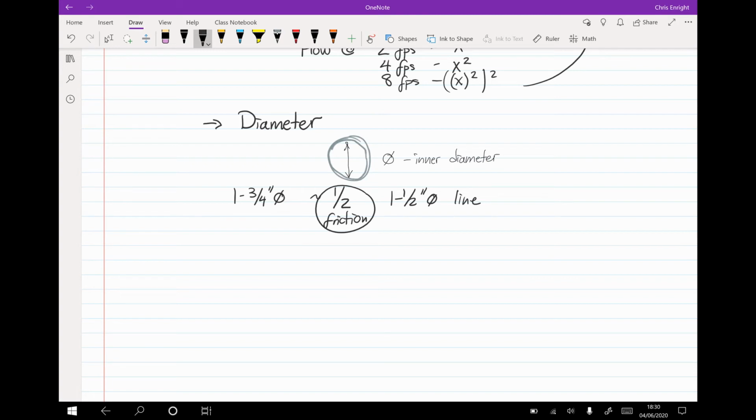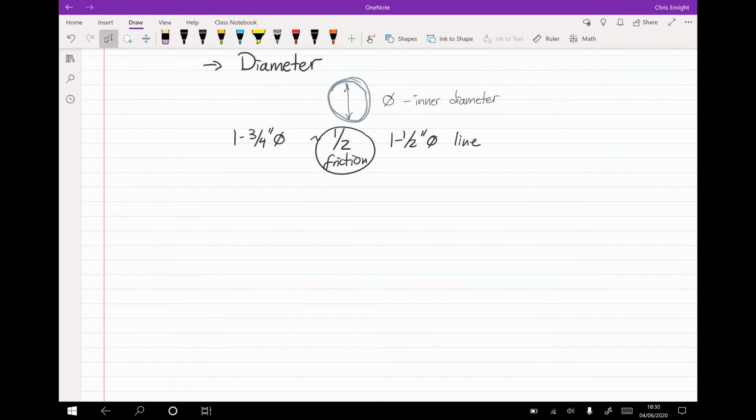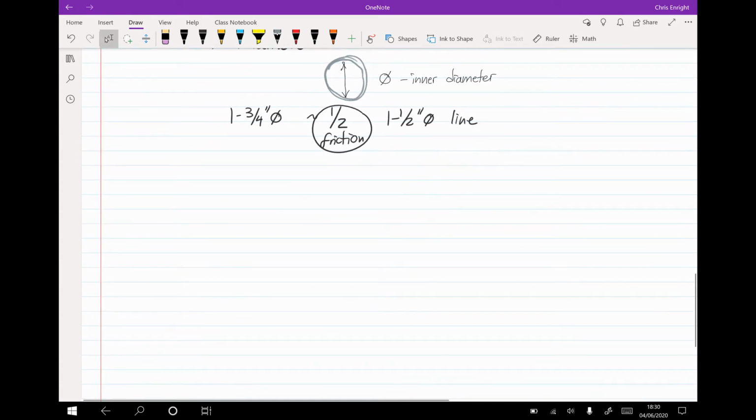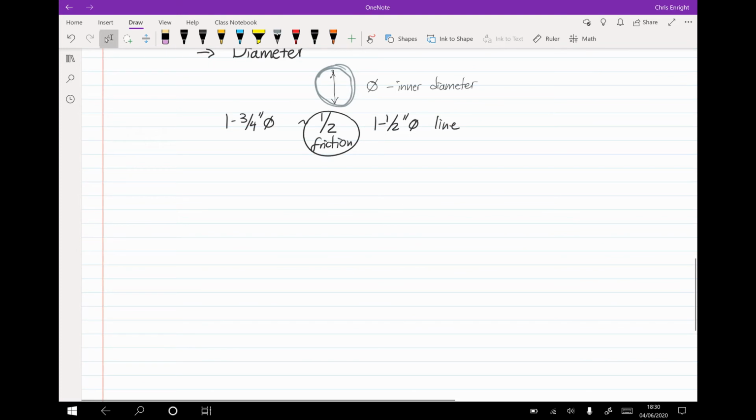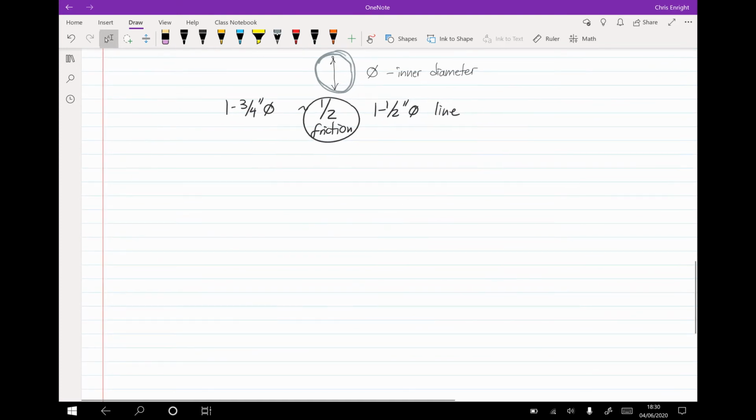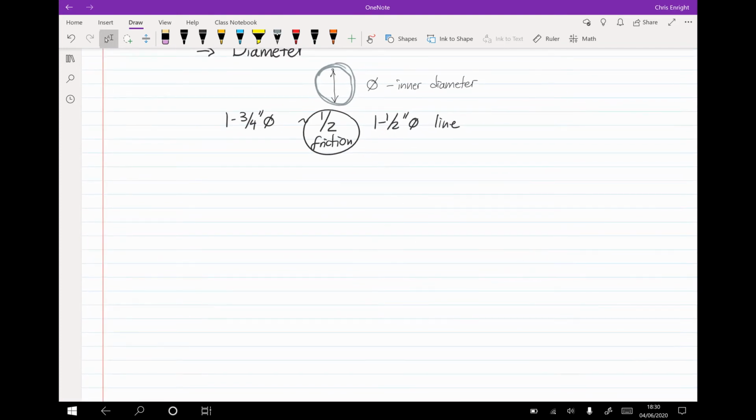Obviously, you could run a garden hose the whole distance. It would just take forever. So if you can use 5-inch, that's the way to go. So it's also the pressure component. Once all other things held equal, pressure doesn't matter. It's just the flow of water through the hose that dictates the friction loss in it, not the pressure at which the water is flowing, if that makes any sense at all.